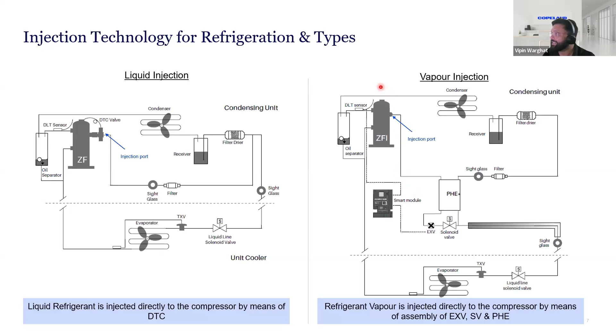It could be liquid injection or vapor injection. So it is basically acting as an equalizer of the refrigeration cycle. It enhances the overall efficiency of the compressor compression, and thus provides energy savings and also enhances the overall envelope of the compressor. Since it also enhances the envelope and bandwidth of compression, it can also produce slightly higher capacity, so the size of the compressor can also be brought down.